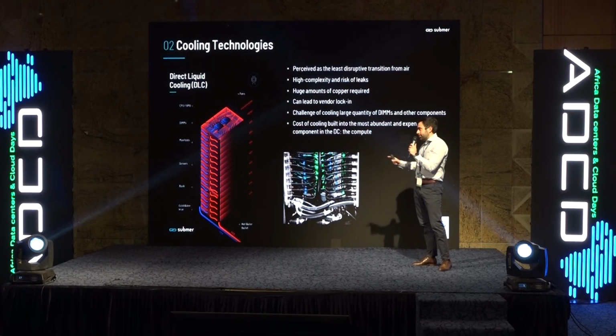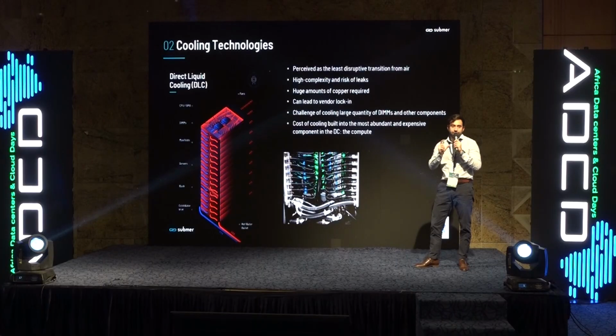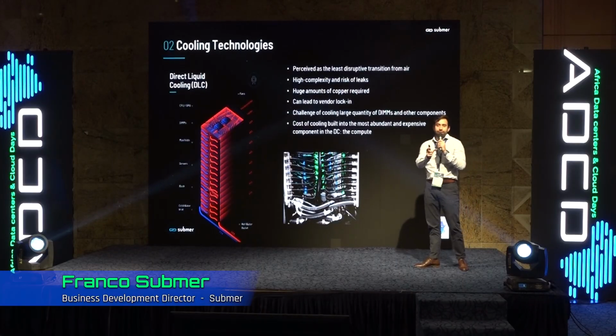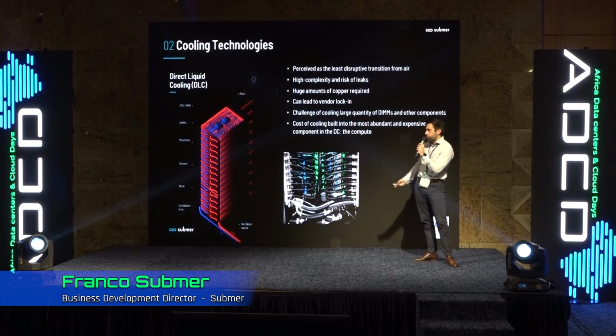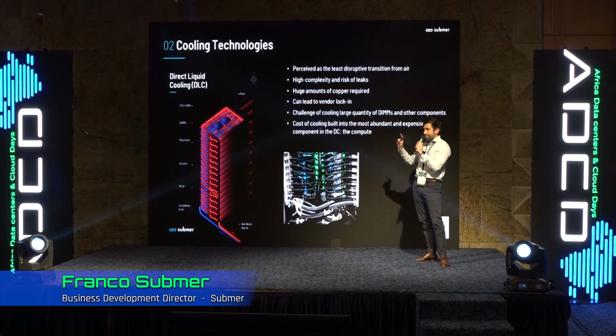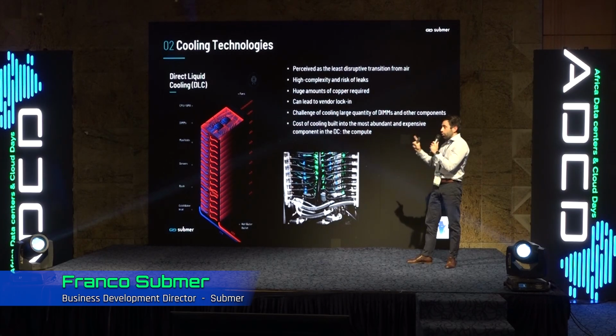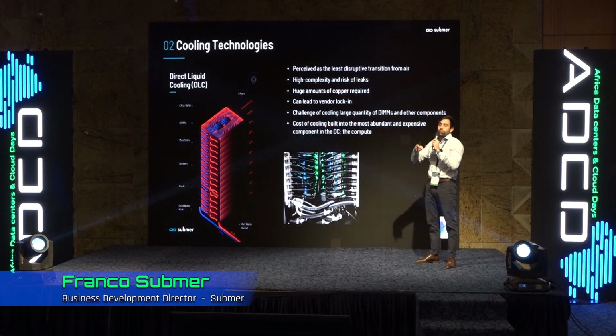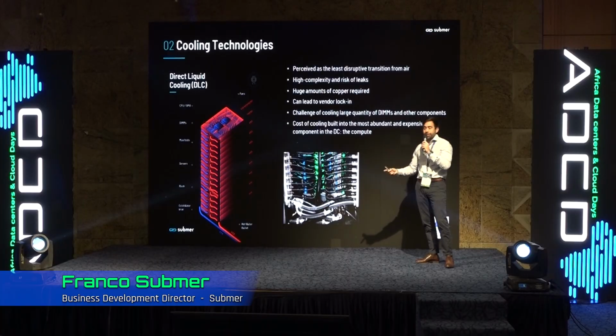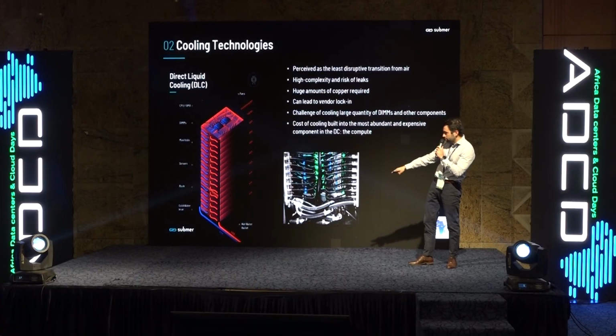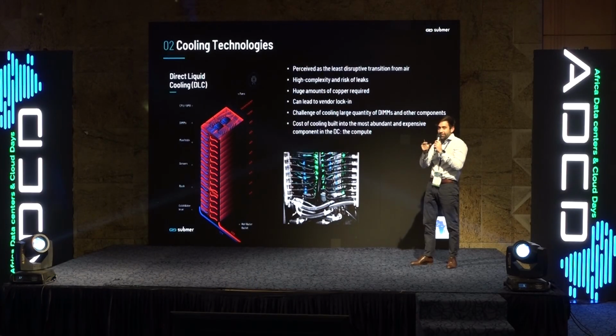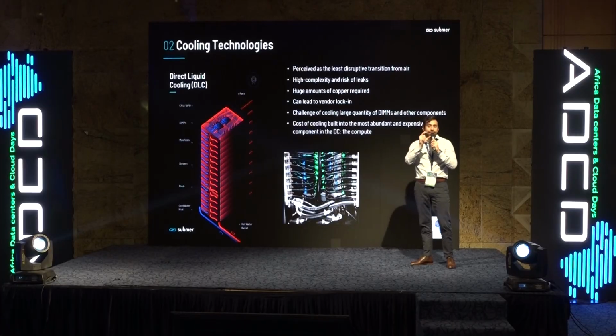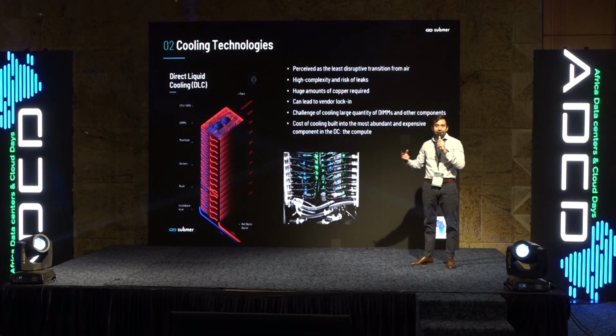One challenge with this technology is vendor lock-in. For instance, Lenovo offers this type of solution, but if you go with Lenovo, you won't be able to use a Dell or HP server, because the manifold and rack design is specific to each vendor, and there's no unified standard.